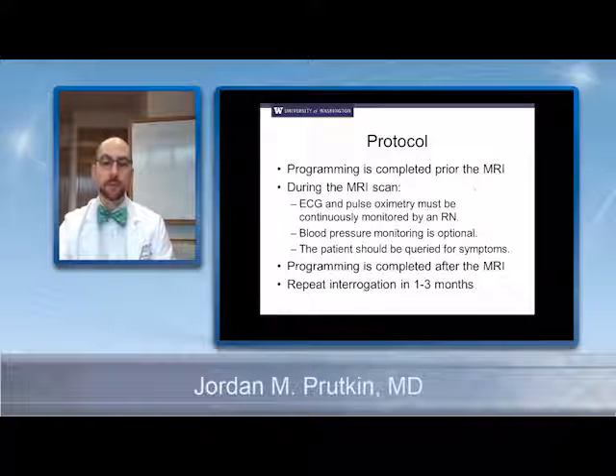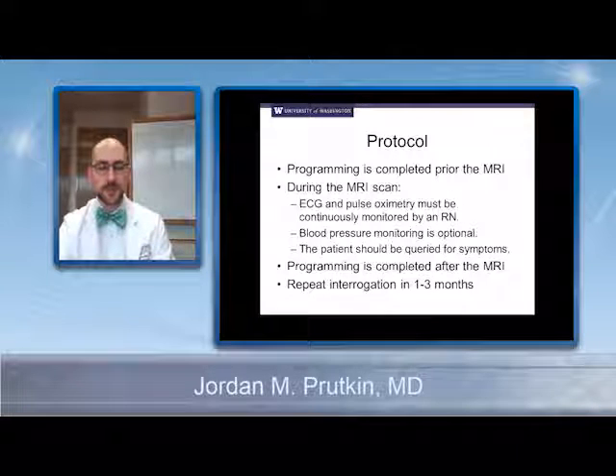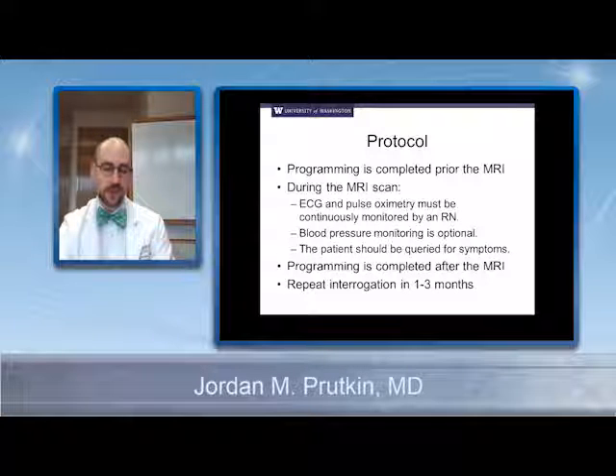And then during the MRI scan itself, we have the patient monitored on ECG and pulse oximetry. So they need to be continuously monitored for this. Depending on the situation, if we have someone who is not pacemaker dependent, we may or may not do blood pressure monitoring. But if we have someone who's pacemaker dependent, or someone who has more significant heart failure and we've had to turn off their biventricular pacing for some reason, then in that situation we would do blood pressure monitoring. And it's sometimes quite difficult.